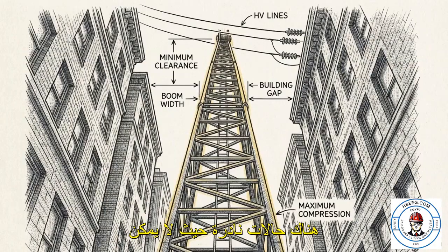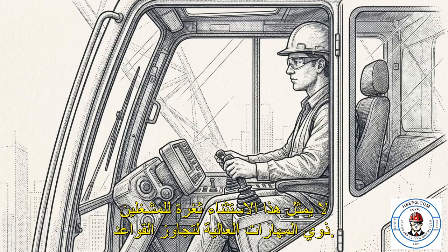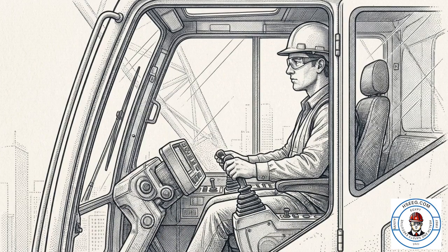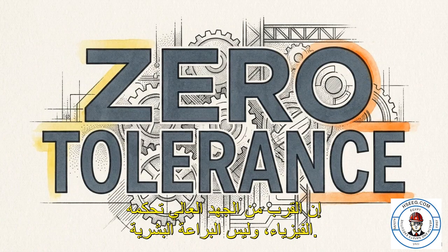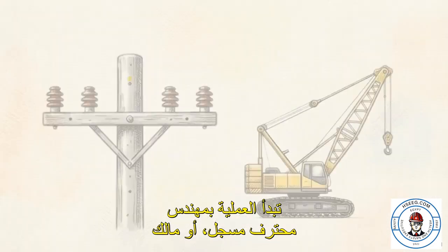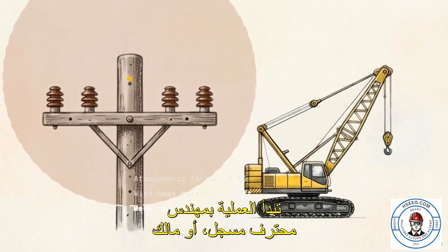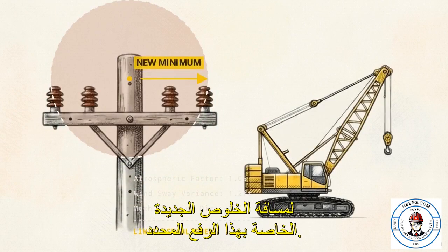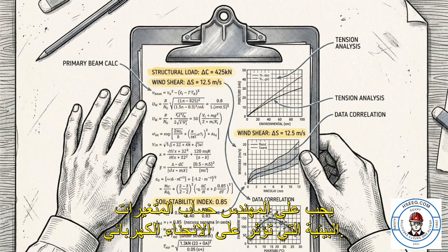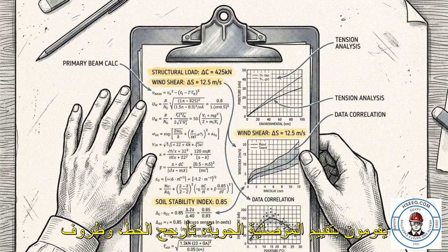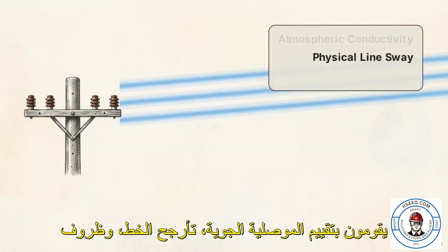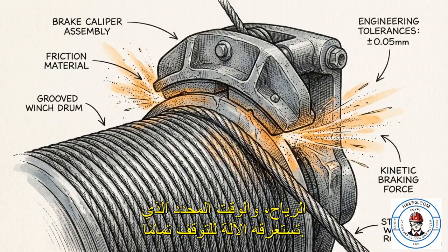There are rare circumstances where a required lift simply cannot be completed from a safe radius. For these situations, OSHA permits a limited exception. This exception is not a loophole for highly skilled operators to bypass the rules. Proximity to high voltage is governed by physics, not human dexterity. The process begins with a registered professional engineer, or the utility owner, calculating a new absolute minimum clearance distance specific to that exact lift. The engineer must calculate environmental variables that affect electrical arcing. They evaluate atmospheric conductivity, line sway, wind conditions, and the exact time it takes the machine to brake to a complete stop.